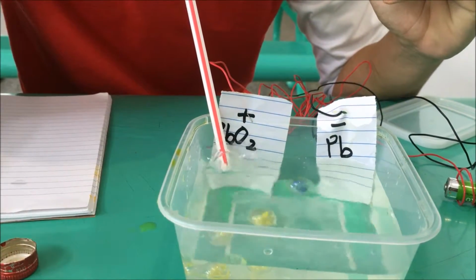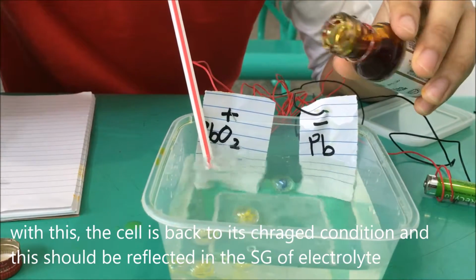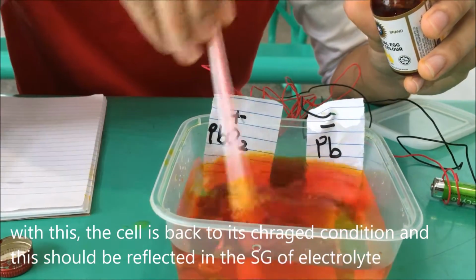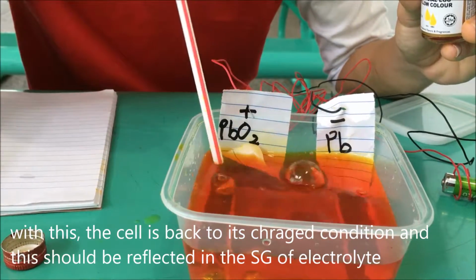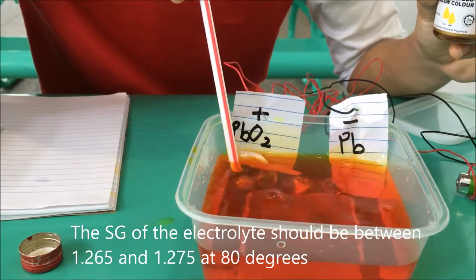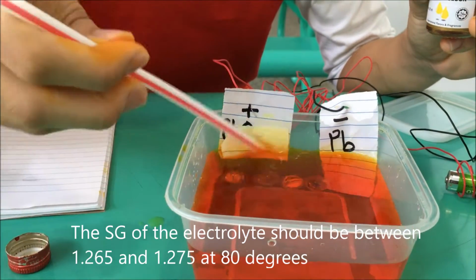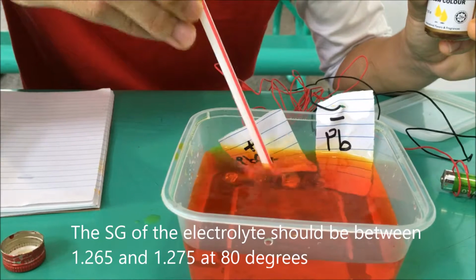With this, the cell is back to its charged condition, and this should be reflected in the specific gravity of the electrolyte. The SG of the electrolyte should be between 1.265 and 1.275 at 80 degrees Fahrenheit.